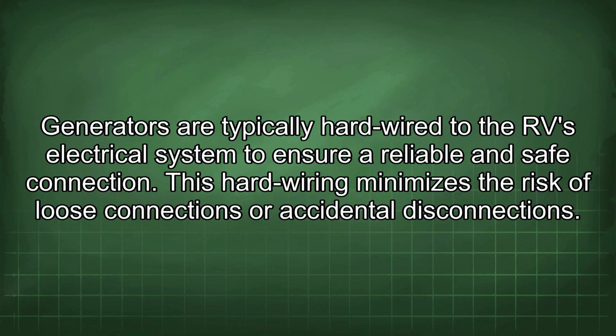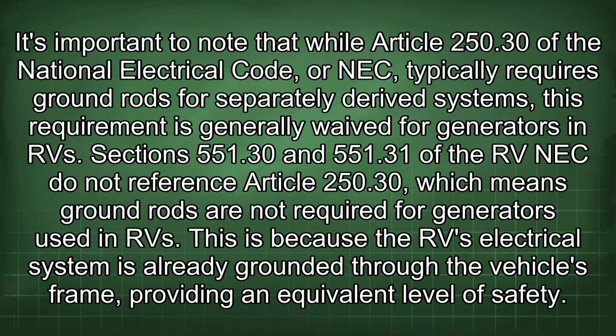Generators are typically hardwired to the RV electrical system to ensure a reliable and safe connection. This hardwiring minimizes the risk of loose connections or accidental disconnections. It's important to note that while Article 250.30 of the National Electrical Code, or NEC, typically requires ground rods for separately derived systems, this requirement is generally waived for generators in RVs. Sections 551.30 and 551.31 of the RV NEC do not reference Article 250.30, which means ground rods are not required for generators used in RVs. This is because the RV electrical system is already grounded through the vehicle's frame, providing an equivalent level of safety.